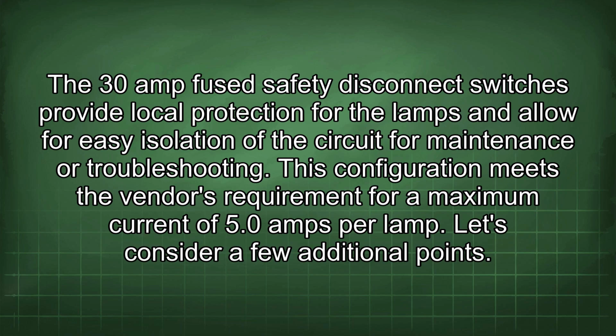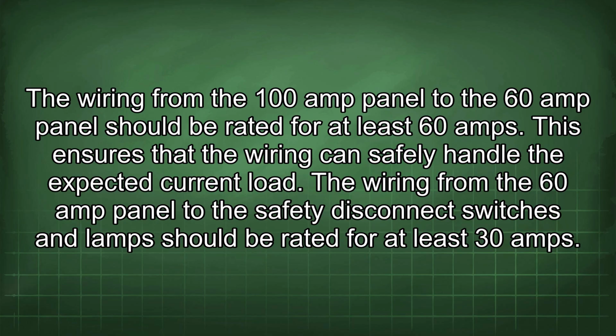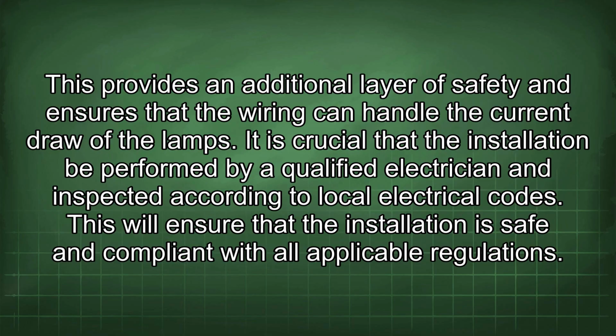Let's consider a few additional points. The wiring from the 100 amp panel to the 60 amp panel should be rated for at least 60 amps. This ensures that the wiring can safely handle the expected current load. The wiring from the 60 amp panel to the safety disconnect switches and lamps should be rated for at least 30 amps. This provides an additional layer of safety and ensures that the wiring can handle the current draw of the lamps. It is crucial that the installation be performed by a qualified electrician and inspected according to local electrical codes. This will ensure that the installation is safe and compliant with all applicable regulations.